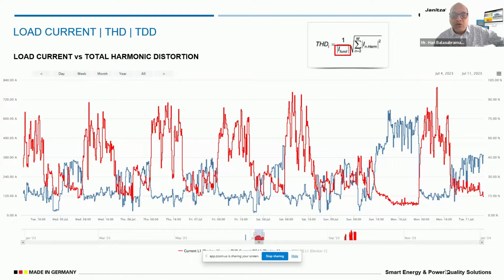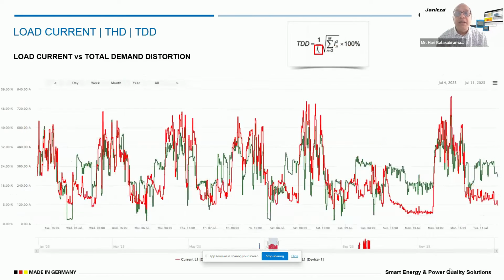So when you are calculating THD, it is always inversely proportional to the load predominantly. So if a VFD is loaded less, the total harmonic current emitted can be higher. And if the load is gaining momentum and the same VFD is fully loaded, then we can see the total harmonic distortion emitted is lower. When it comes to the total demand distortion, it is based on the nominal load in the system over a period of time.